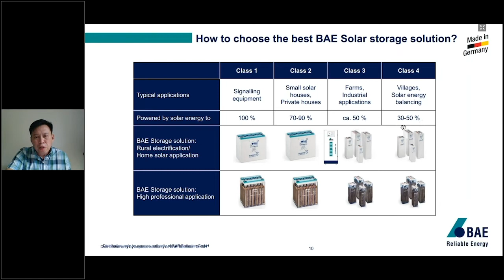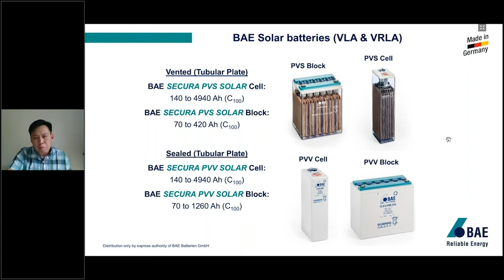We have as low as 2 volt, 140 Ah, up to 4,940 Ah for the biggest cells we can supply, especially for big solar and even wind applications. The only thing you have to decide is between VLA, known as vented lead acid, and VRLA, valve regulated lead acid. The difference is vented needs to be topped up periodically with pure distilled water, whereas the sealed type doesn't need topping up - that's why it's called maintenance free.